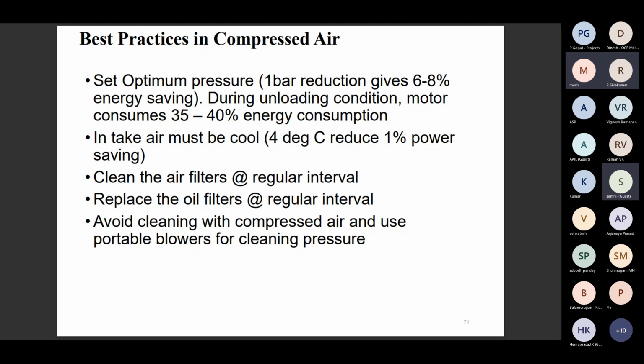If any compressor is loaded below 70 to 80%, say on the safer side below 70%, with unloading at 30%, it means there is potential to retrofit a VFD to reduce the unloading power. Whenever the compressor is running, it generates air only during the loading time. During unloading time, air is not generated because the cylinder is not activated with the motor. Only the motor is idly running. During this period, 35 to 40% of the rated power of the motor will be consumed during this unloading condition.